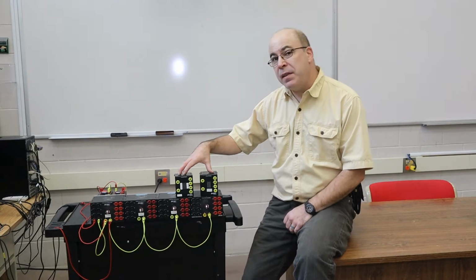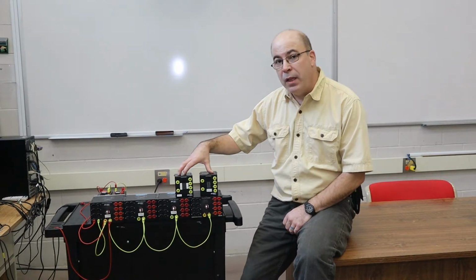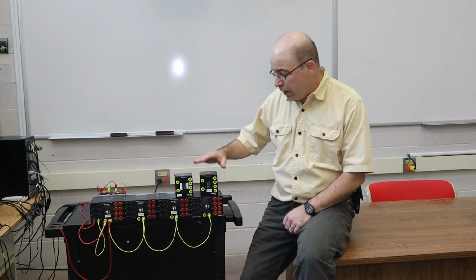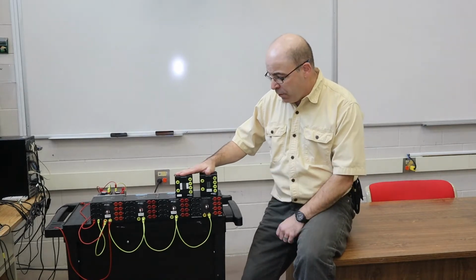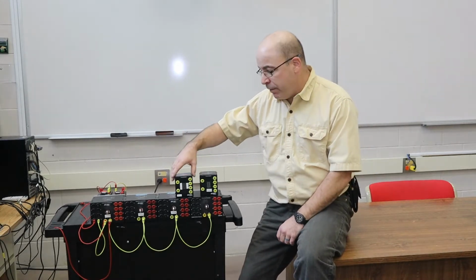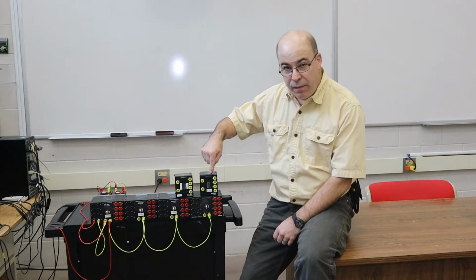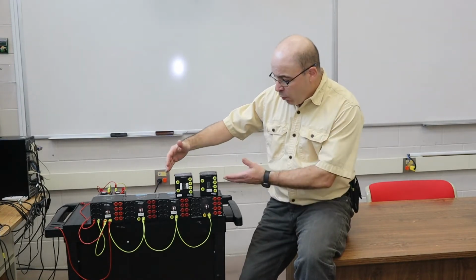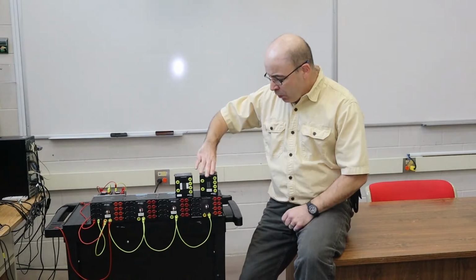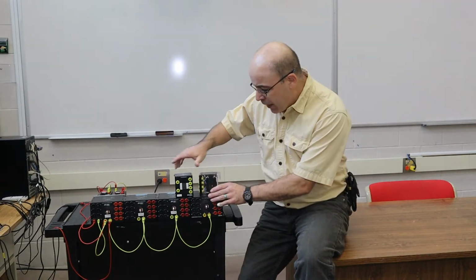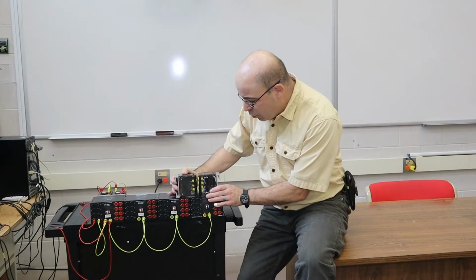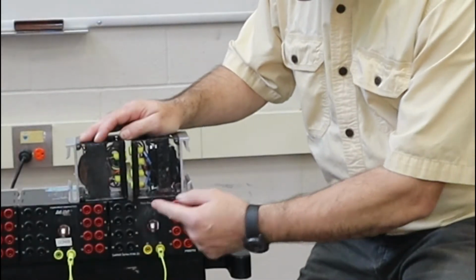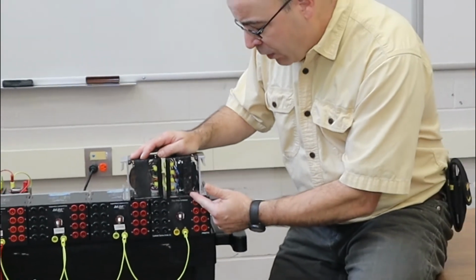Today we're going to demonstrate the properties of how to size a control transformer and the importance related to it. Here I've got two control transformers, one rated at 50 VA and one at 25 VA. Now, of course, inside of the enclosure, it doesn't mean much, but let me turn these transformers onto their side so we can do an actual comparison. We can see the differences in between both transformers.